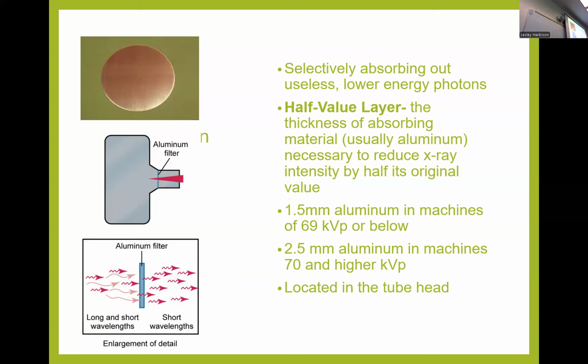The location of this, just to clarify, is not part of that little glass tube that actually generates the X-ray photons. It is basically at the base of the PID. You can go into the X-ray room and look straight down the PID and you can see metal, and that's what you're looking at, basically that filter. There could be a plastic covering or something, I suppose, but that's basically where this filter is. It's right at the back end of the PID.